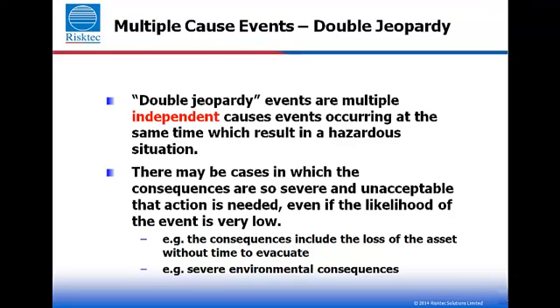The normal approach to a HAZOP is to consider only single failure events. However, in some cases it may be necessary to consider multiple failure cases. So-called double jeopardy events are multiple, independent events which occur at the same time. These events conspire to cause a hazardous situation. Double jeopardy events are not common, but they do occur. And even where the likelihood is very small, the consequences may be of such catastrophic proportions that provision has to be made to provide safeguards against them.